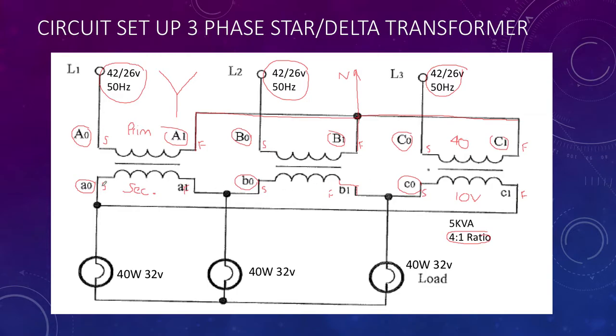If we start with the A phase, you'll notice that our finish is connected to the start of B phase. There's our first link. Then the finish of B phase is connected to the start of C phase. And then finally, our finish on our C phase is then connected all the way back to the start of A phase. So our transformer on the output side, or secondary side, is a delta-shaped winding.